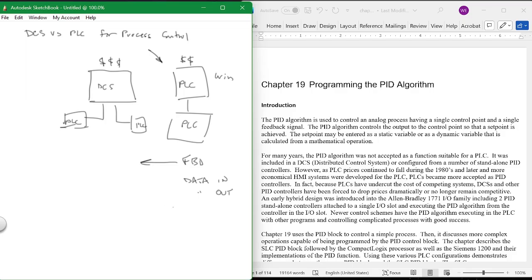And the general rule is if you're on a pulse and on a clock, and every clock cycle you execute your program, you get the data within 10% of when it's executed. So within 10% of the time that it takes to get it. In other words, the data is not back here, it's right in this little area right here. So you collect it, then you execute, then you're good. You collect it, you execute, and you're good.